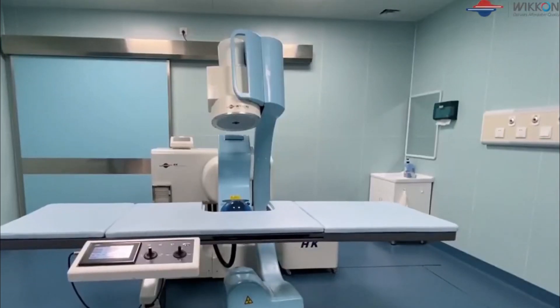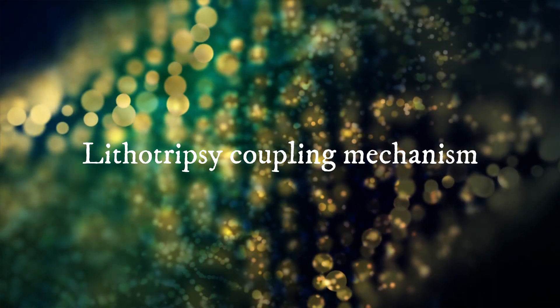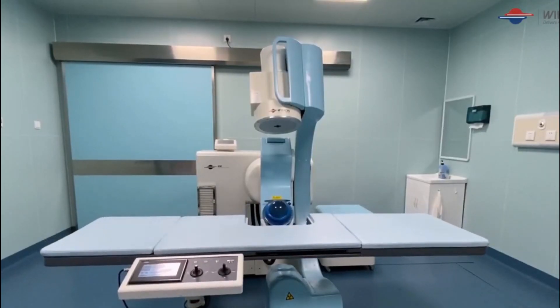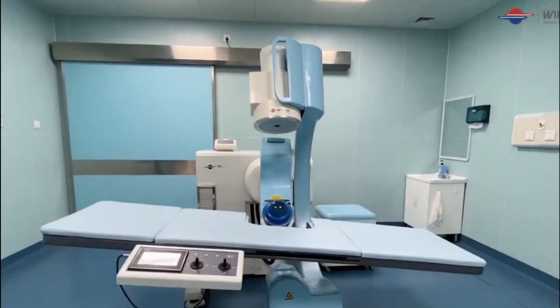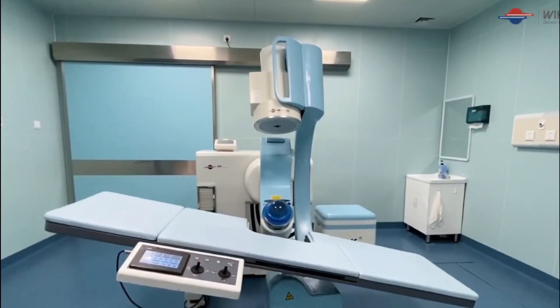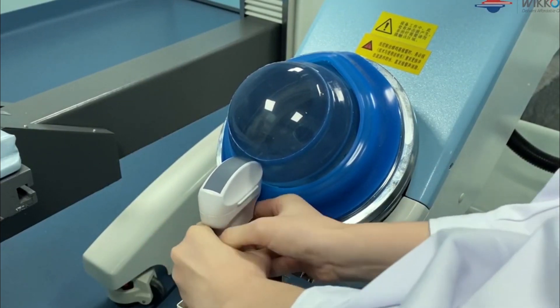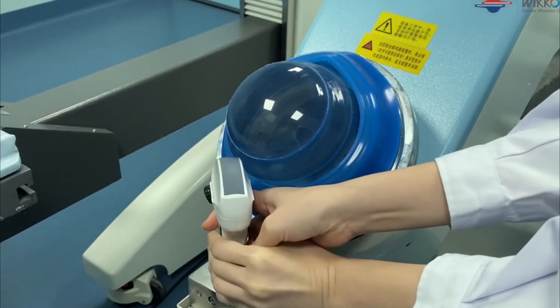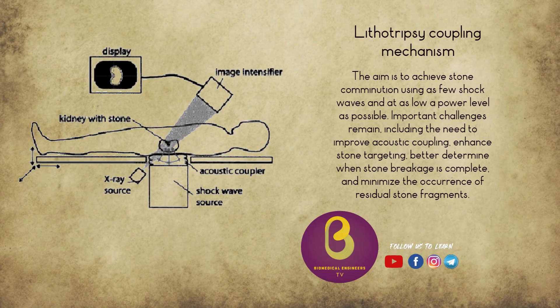The third component is the coupling mechanism. In the propagation and transmission of a wave, energy is lost at interfaces with differing densities. A coupling system is needed to minimize the dissipation of energy of a shockwave as it traverses the skin surface. The usual medium used is water, as this has a density similar to that of soft tissue and is readily available.